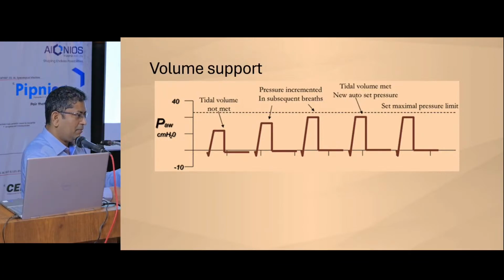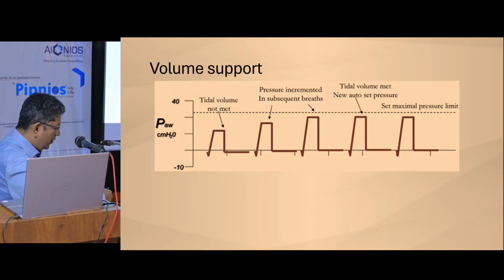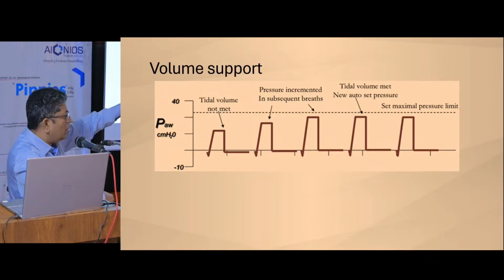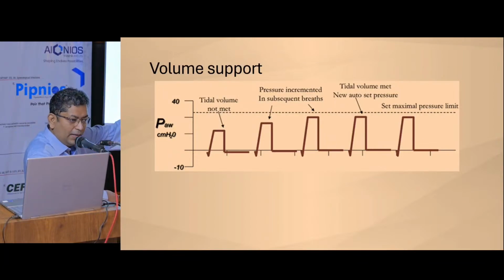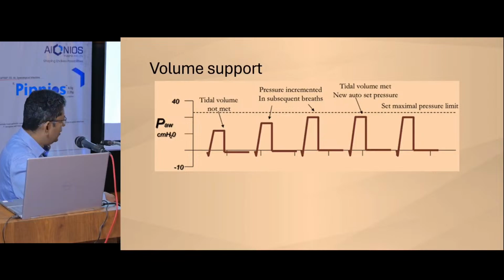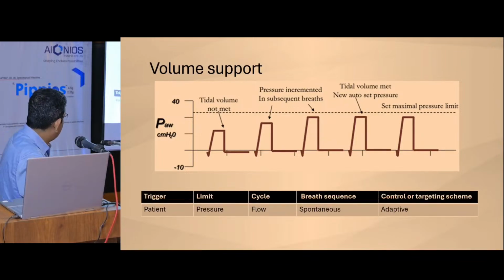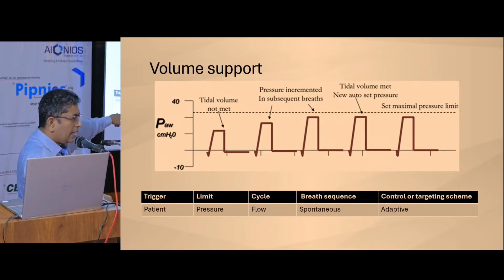For volume support, the pressure keeps on changing as you set a tidal volume, and to get the tidal volume, the pressure support keeps on changing. That's what we do. We do set a maximal pressure limit so that the ventilator will not give more than that. Even for PRVC we do that. So the trigger is patient, limit is pressure, cycle is flow, not time.